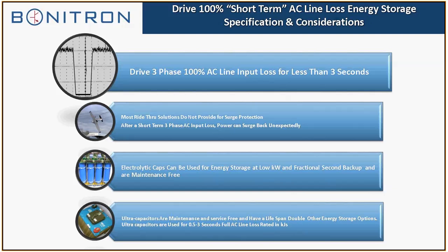So now short-term outages, all 3 phases, 100% AC line loss. We used to say less than 3 seconds. Now we say less than 5 seconds, because now we've configured the heavy-duty M3460Bs, the heavy-duty boosters, which are rated at 4 minutes, to be able to do the UltraCaps, which are greater than 2 seconds. You're limited with the SAG ride-throughs if you add UltraCaps to them, because they will time out at 2 seconds.